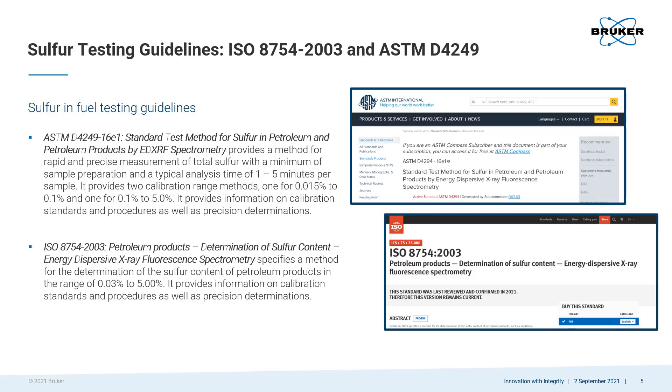There are authorized testing methods to determine compliance with the MARPOL sulfur regulations. Energy dispersive x-ray fluorescence, or EDXRF, is utilized in two of those methods. They are ASTM D4294-16E1, standard test method for sulfur in petroleum and petroleum products by EDXRF, and ISO 8754-2003, determination of sulfur content in petroleum products with EDXRF.